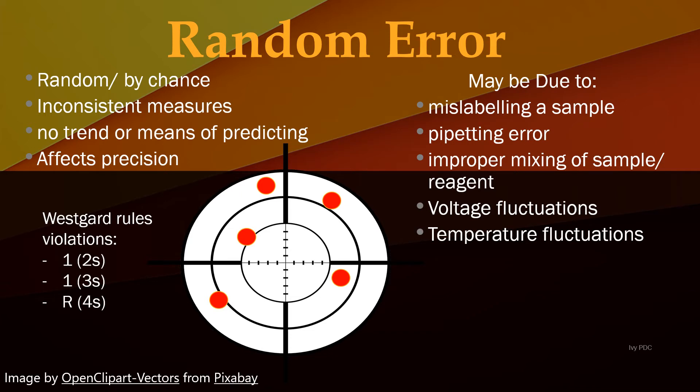All of these different measurements would give a scattered plot because of the different causes of the errors. If a random error occurs, the same mistake may not be made again. The different Westgard rule violations for random errors would be 1-2s, 1-3s, and R-4s.